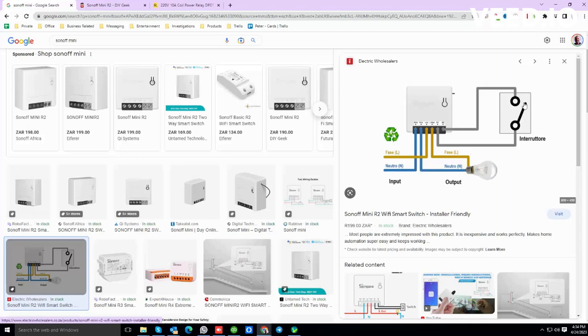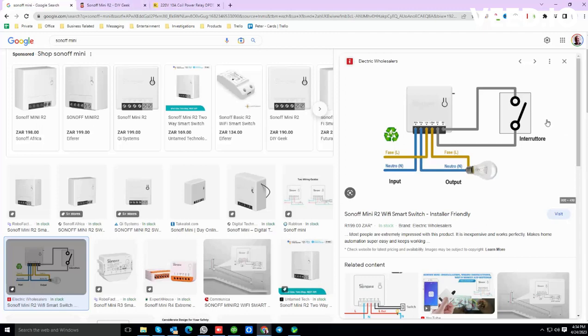You'll connect that to those two contacts there and the other side of the coil you'll have your 220 volts in. You would connect that to your Eskom mains or your municipal mains, and that will change the state of the switch when Eskom is on or off.